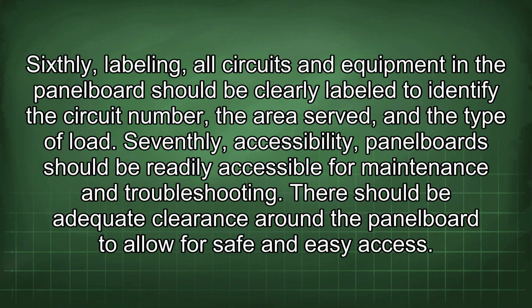Sixthly, labeling. All circuits and equipment in the panel board should be clearly labeled to identify the circuit number, the area served, and the type of load. Seventhly, accessibility. Panel boards should be readily accessible for maintenance and troubleshooting. There should be adequate clearance around the panel board to allow for safe and easy access.